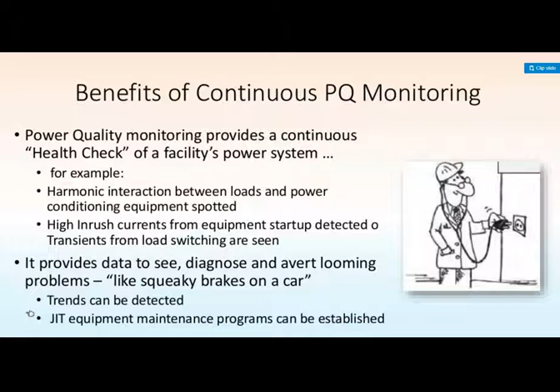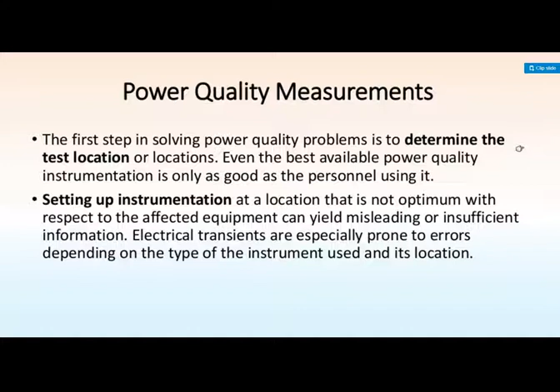Now, power quality measurements. The first step in solving power quality problems is to determine the test location. Even the best available power quality instrumentation is only as good as the personnel using it, and setting up the instrumentation at a location that is not optimum with respect to affected equipment can yield misleading or insufficient information. Electrical transients are especially prone to error depending on the type of instrument used and its location. These are the main two steps for power quality measurement.